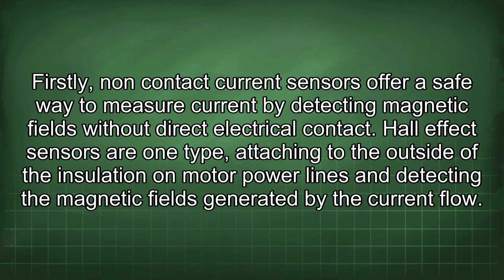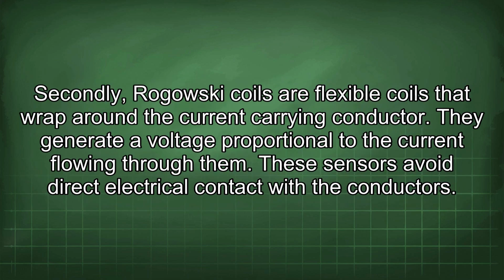Hall effect sensors are one type, attaching to the outside of the insulation on motor power lines and detecting the magnetic fields generated by the current flow. Secondly, Rogowski coils are flexible coils that wrap around the current-carrying conductor. They generate a voltage proportional to the current flowing through them. These sensors avoid direct electrical contact with the conductors.